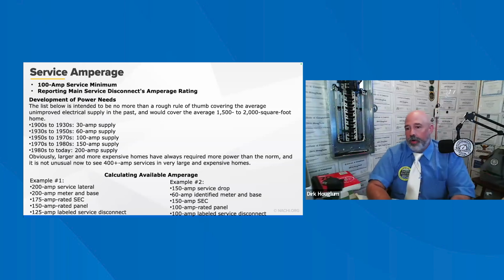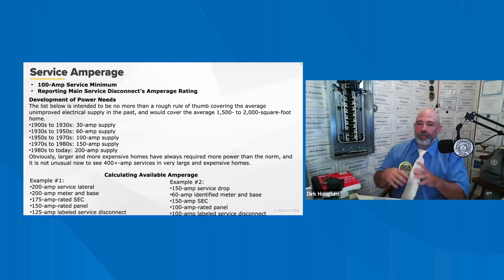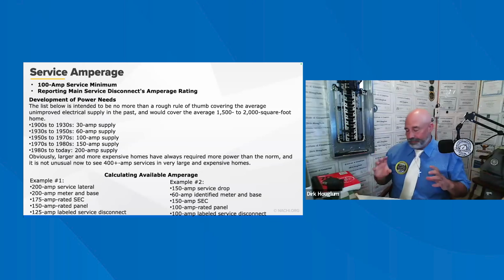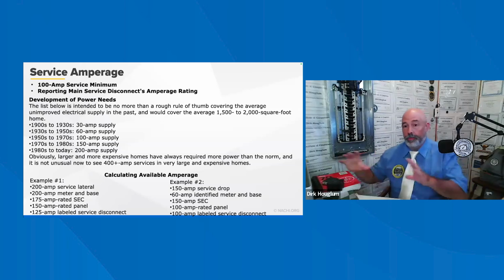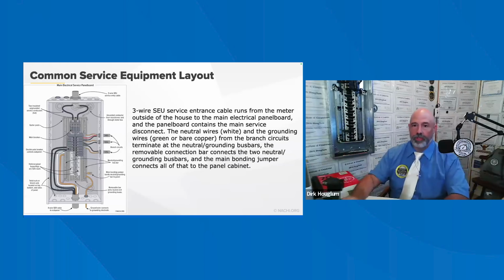One way a home inspector can help communicate the available amperage is to determine the lowest rating, or the weakest link: the service supply, the service meter, the conductors, service disconnects, things like that. Here's a couple examples. A home inspector should describe the rating. The home inspector may also describe the 60 amp meter as a potential indication. That's why I showed you those pictures earlier. The home inspector is not an electrician, and we must be careful in describing the total amperage of the service supply to the house. Follow the standards of practice, and use words like "it appears to be" instead of "this is 60 amps." No, it appears to be 60 amp service. So your wording can really help you in that.